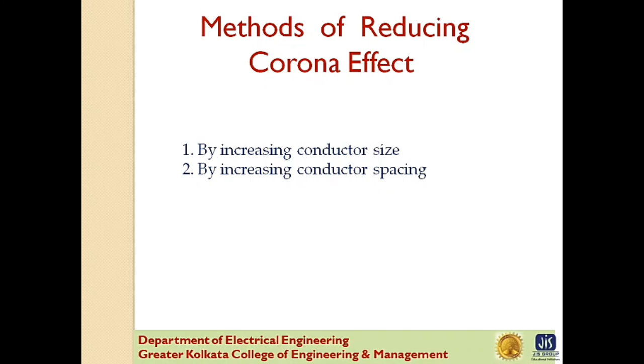Now, we solve problems. The first problem is: a three-phase line has conductors 2 cm in diameter spaced equilaterally 1 meter apart. If the dielectric strength of the air is 30 kV per centimeter, this is the maximum value, find the disruptive critical voltage for the line, given the air density factor delta equal to 0.952 and irregularity factor 0.9.